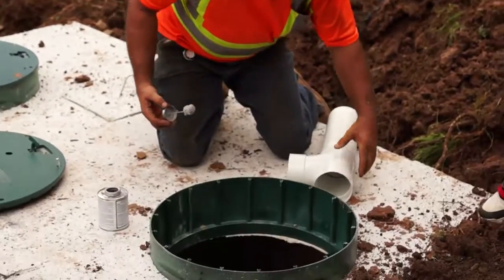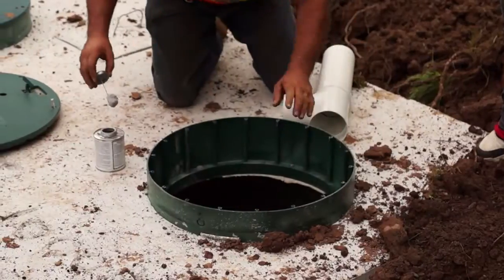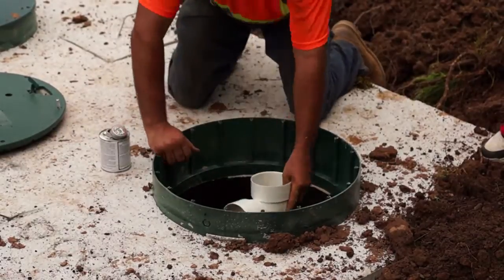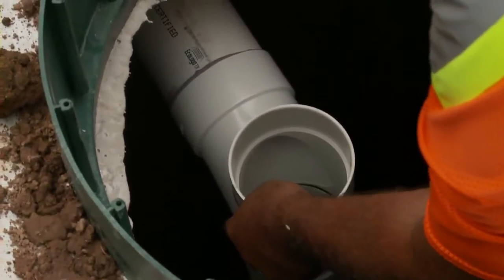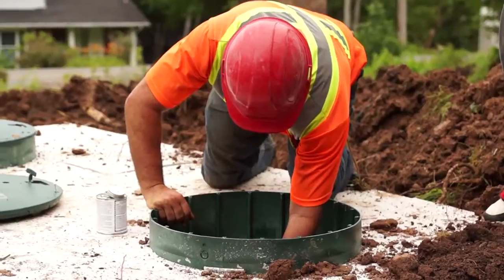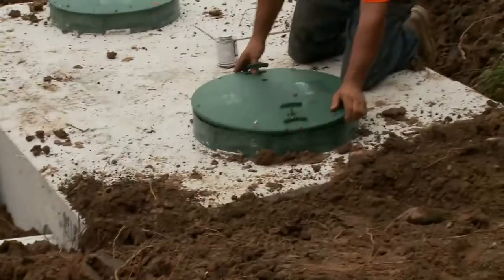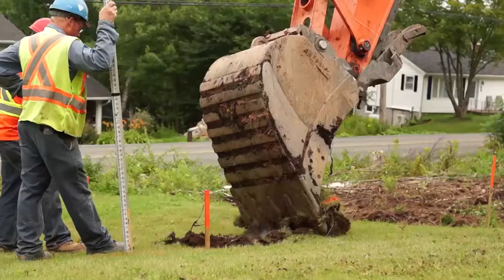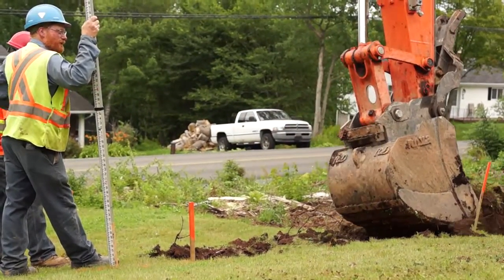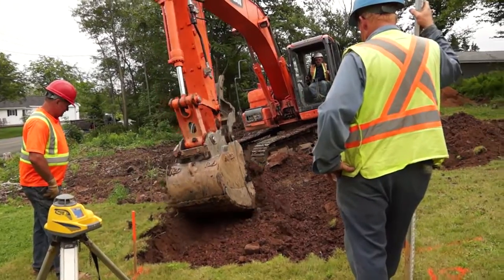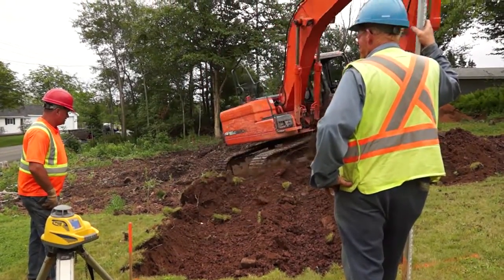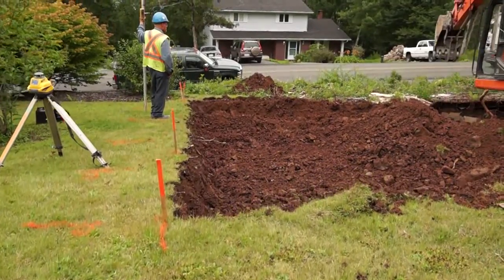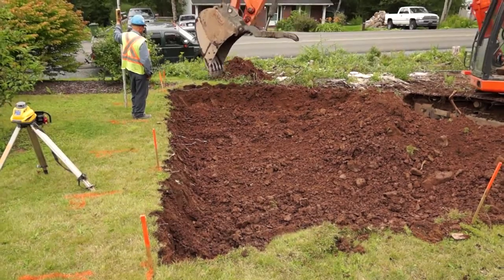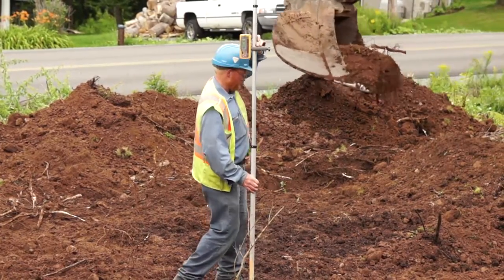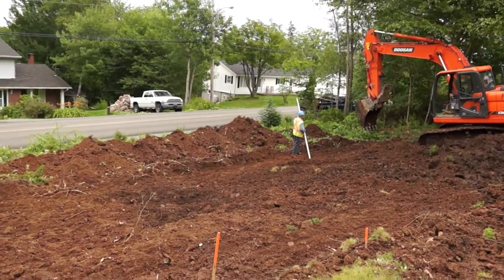A baffle or T is placed in the tank on the end of the inlet pipe. The natural soil is excavated from the area of the bed to the dimensions shown on the design. The bottom of the excavation must be level across its width and have a uniform slope as specified on the design.